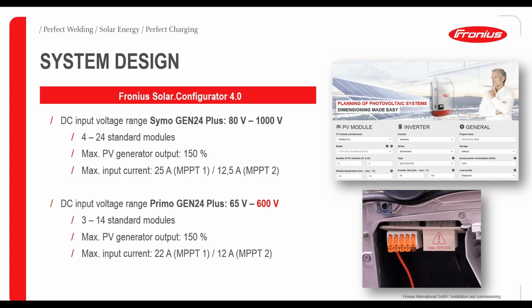modules within a string. And on every device, also on the SnapInverters, it is possible to over-dimension our inverter up to 150%, which means on a Symo Gen24 10 kilowatt device, we can connect 15 kilowatt peak onto the device without any damage or warranty issues. So this is possible on every device. And please make sure the input current is different between the MPP trackers: the first one, as I mentioned, 25, the second one, 12.5 amps.